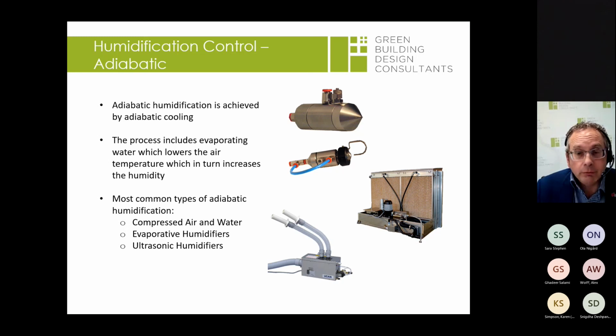So we recently fitted one of these adiabatic coolers on a large contact lenses clean room facility. We had to raise the temperature up to about 35 degrees, and then as it dropped through the adiabatic cooler - again, these are all quite large volumes - it dropped to about 18, and then we had to have another reheater to take that air up from 18 to about 21. The more you heat it up, the more it drops.